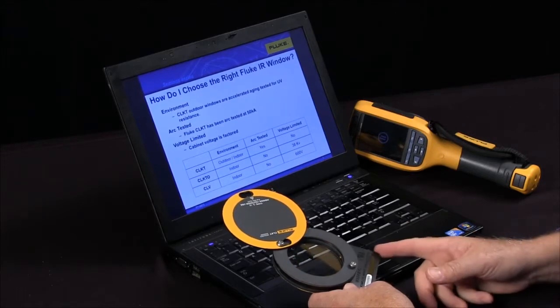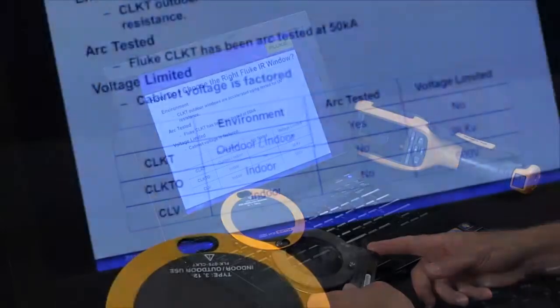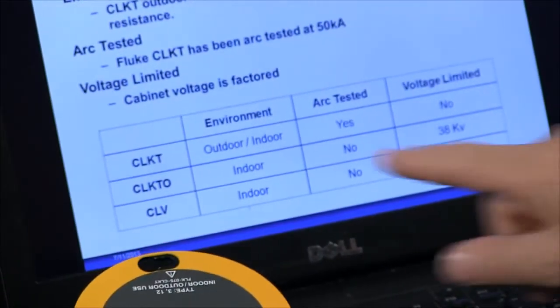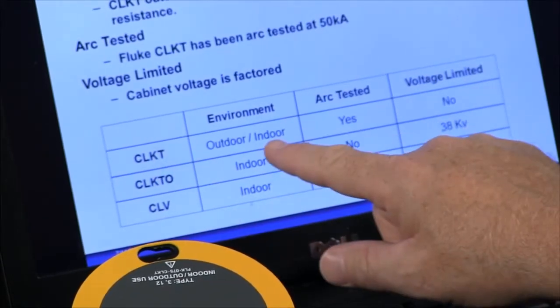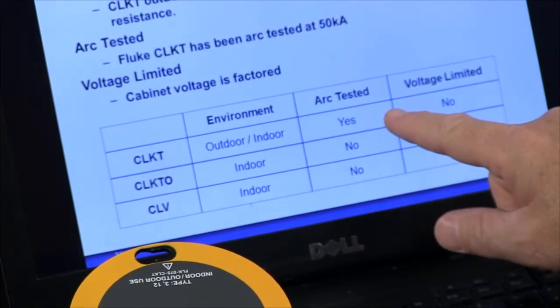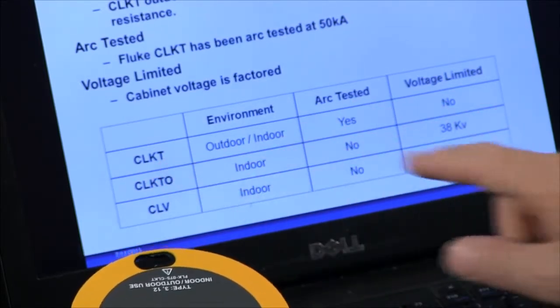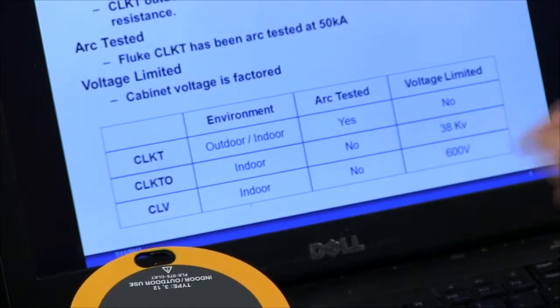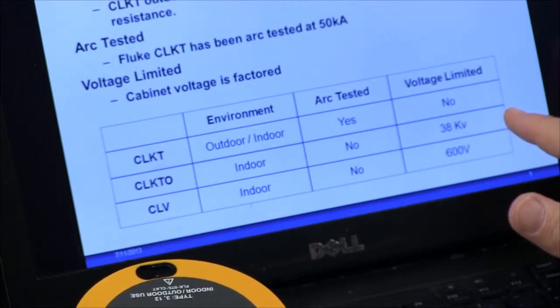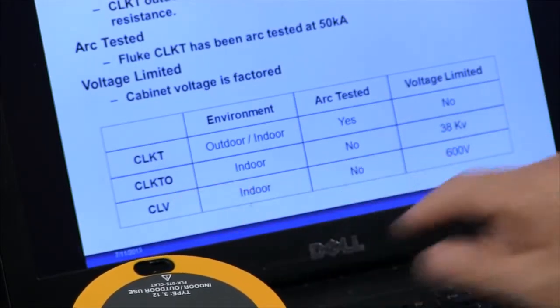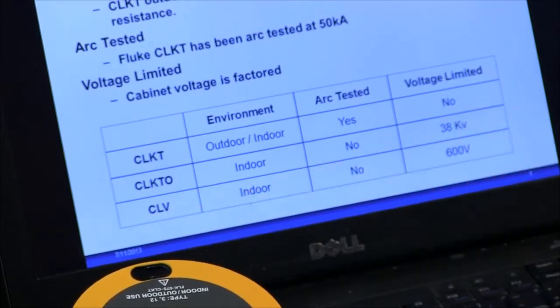Fluke actually has models that are rated for the outdoors and will stand up to UV because they're tested to UV aging testing. So if it's an outdoor application you would select the CLKT model. If it's an indoor application and it's going into an arc tested cabinet, then that will also be a CLKT model. If it's indoors in a non-arc tested cabinet and you need to go up to 38 kV with switchgear, then you'll have the CLKTO. If it's 600 volts or lower, let's say a 480 volt cabinet, will be the CLV.